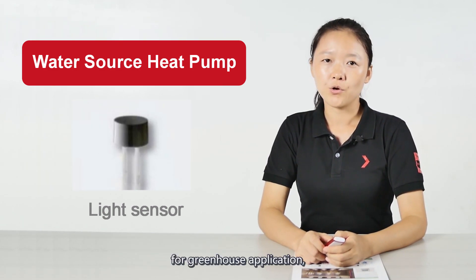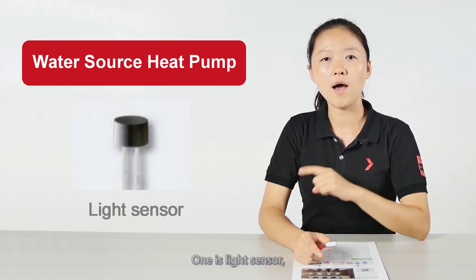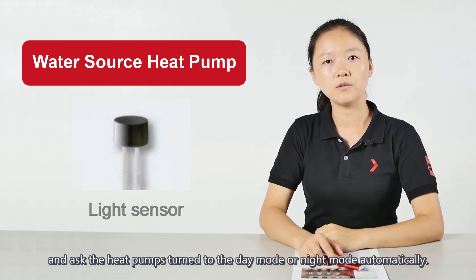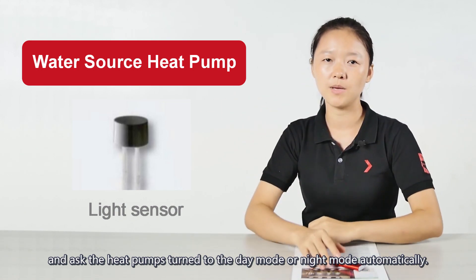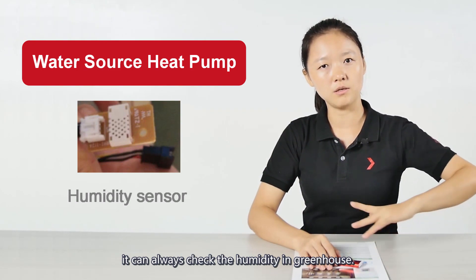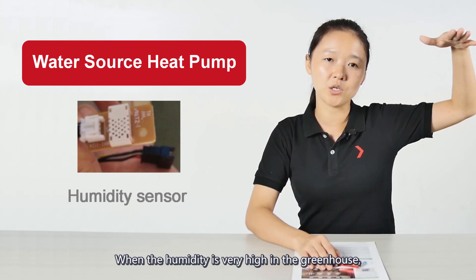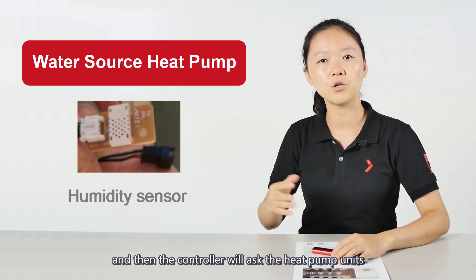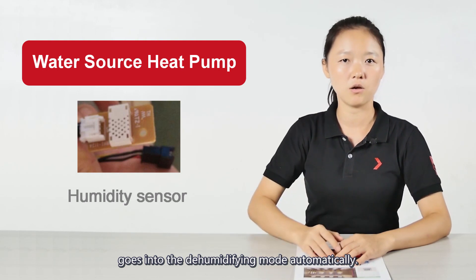For greenhouse applications, there are also two additional sensors. One is a light sensor, which sends a signal to the heat pump and asks it to switch to day mode or night mode automatically. The other is a dehumidifying sensor, which constantly checks the humidity in the greenhouse. When humidity is very high, it sends a signal to the controller, and the controller will ask the heat pump units to enter dehumidifying mode automatically.